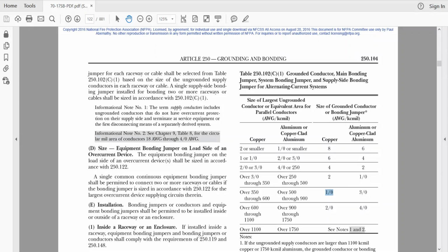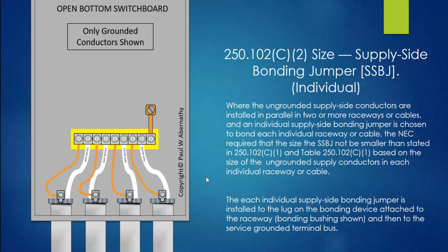So now let's go back to the PowerPoint. All right, so that's what this jumper would be. And you know what? It's readily available to find a 1/0 rated lug that can handle 1/0, a lot more than you might find one that handles 250 kcmil. If you can find one and you want to run a single one through it, that's fine. But a lot of times this is the application that people use.